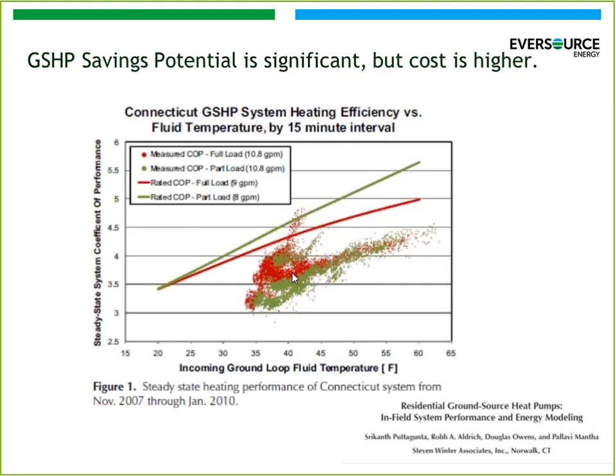I would characterize this as a good performing ground source heat pump. It looks like it's got a measured COP approaching 4. And back to your earlier questions, if we looked at some of the newer ground source heat pumps that are out there, these rated lines would shift up probably to the 4.5, 5, and maybe even 6 COP range, and hopefully we'd expect the actual performance to also shift up and follow suit. So I'm sure there's probably actual COPs out there that are in the 4 to 4.5 range for ground source heat pumps.